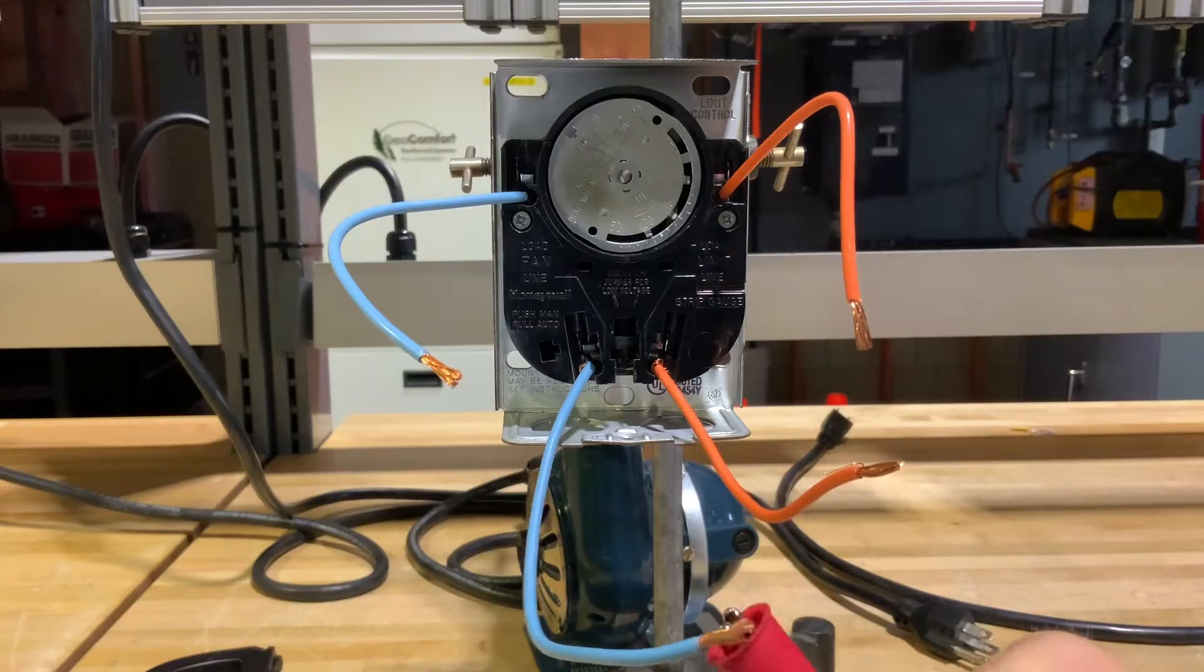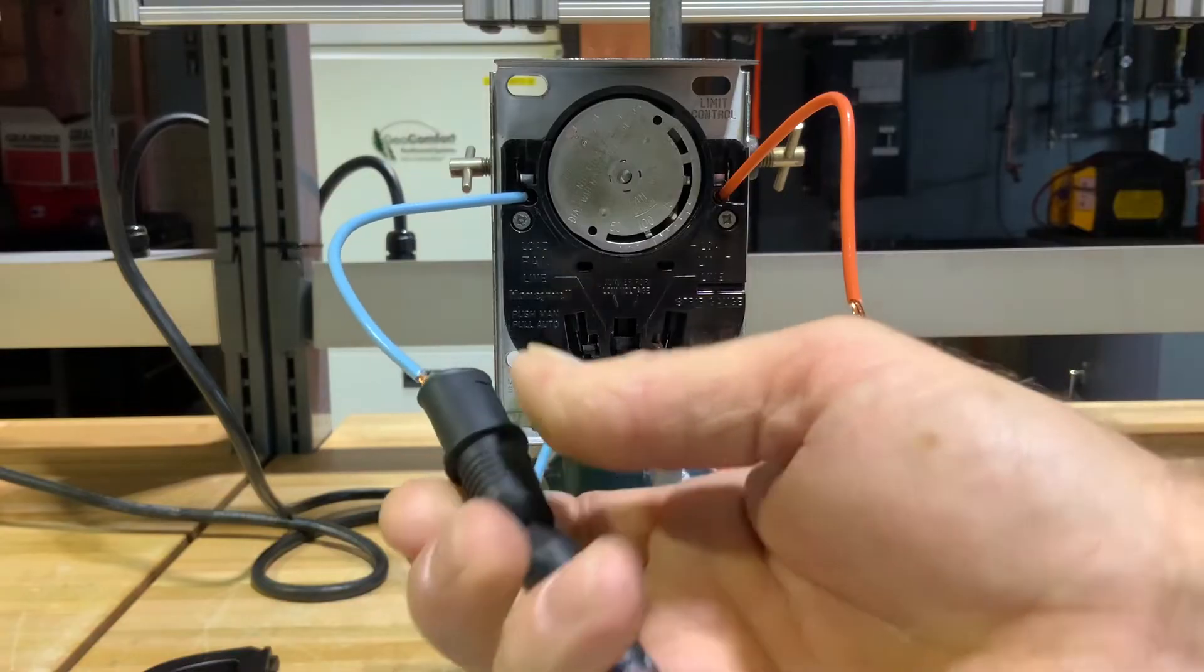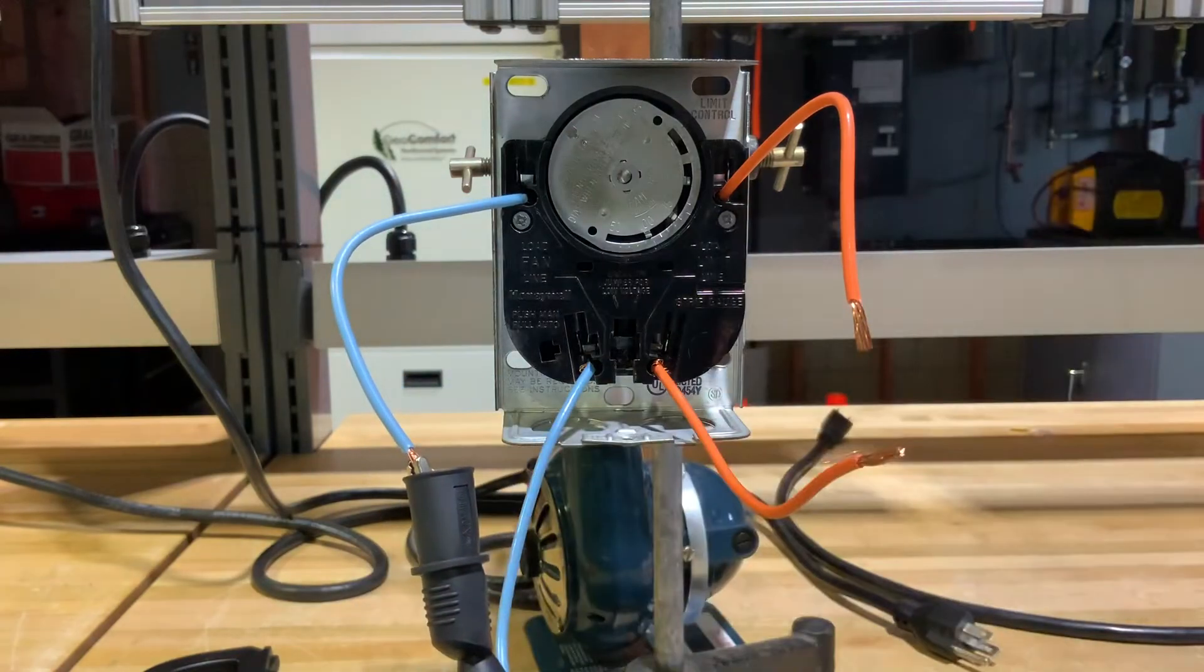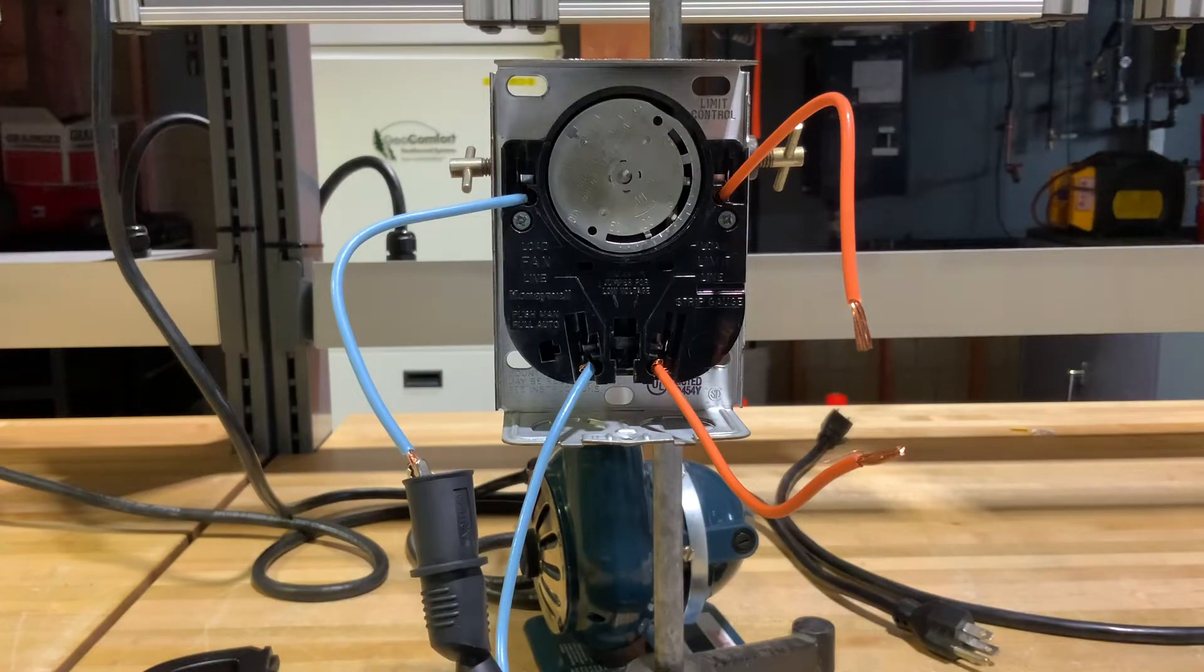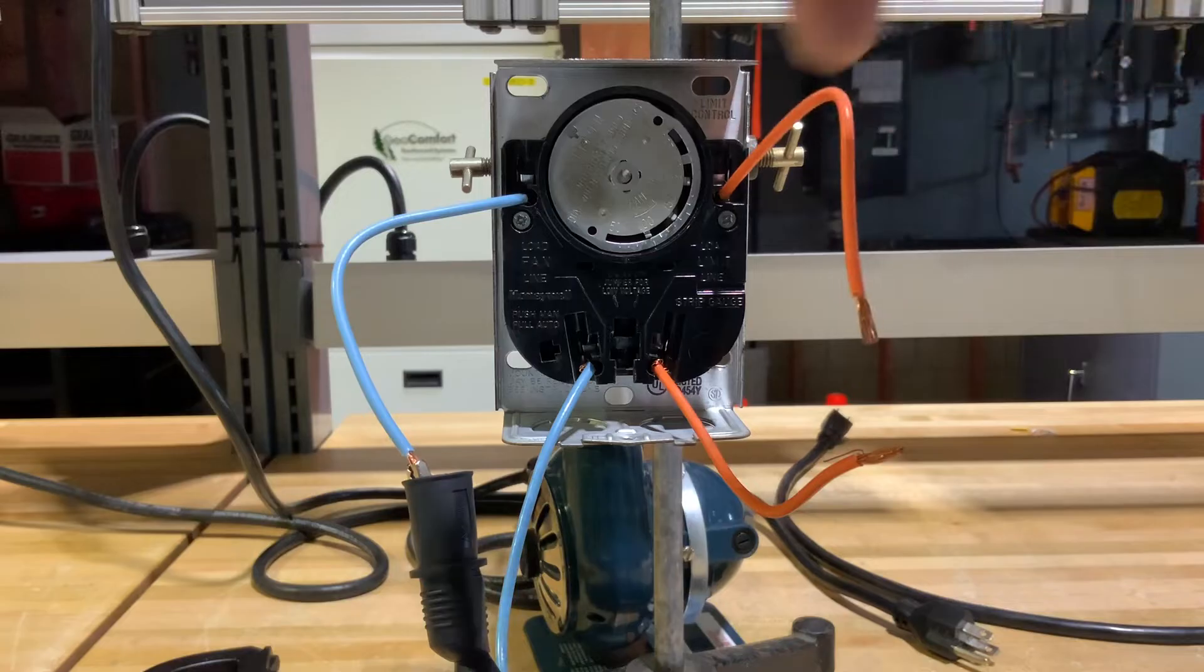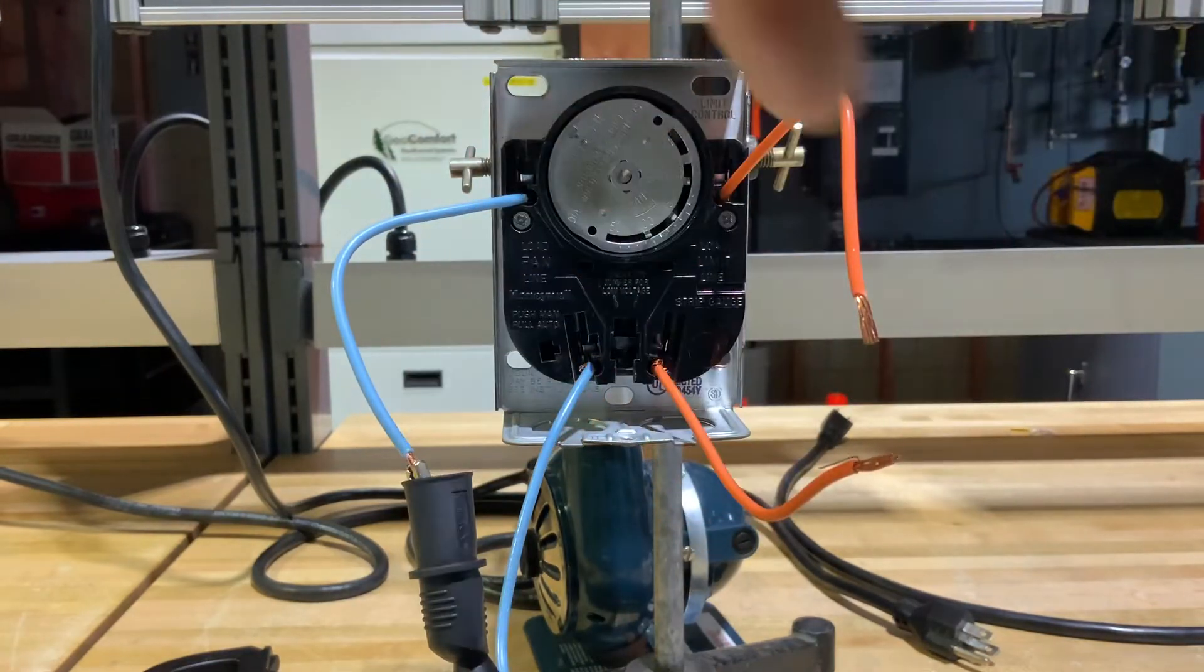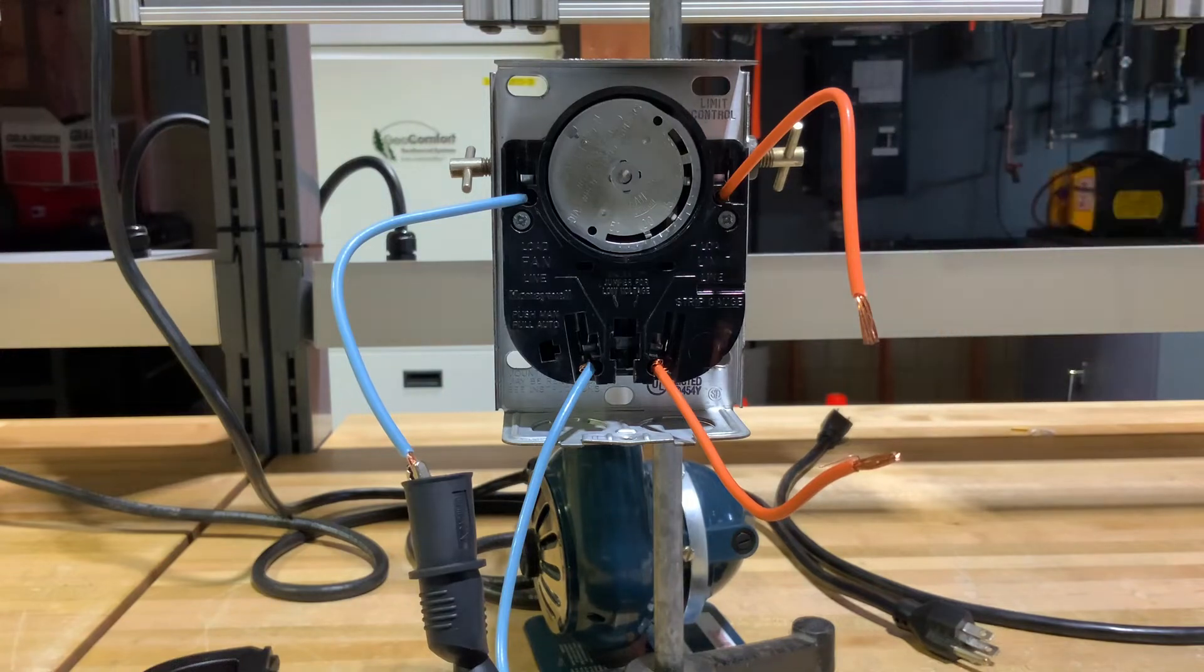If I check the fan side of it, we have no continuity through the fan side. So from the circuit breaker, power comes into our limit, goes out of our limit. From here it goes to power up our primary control unit.